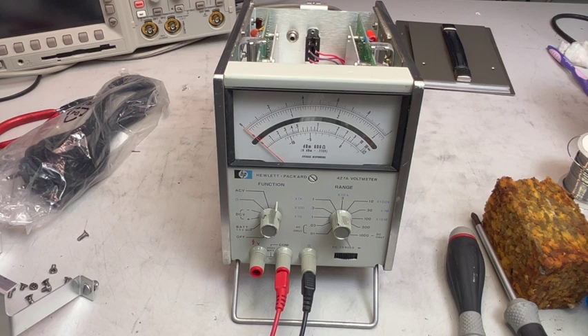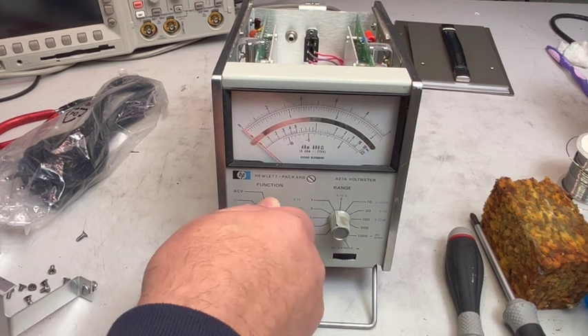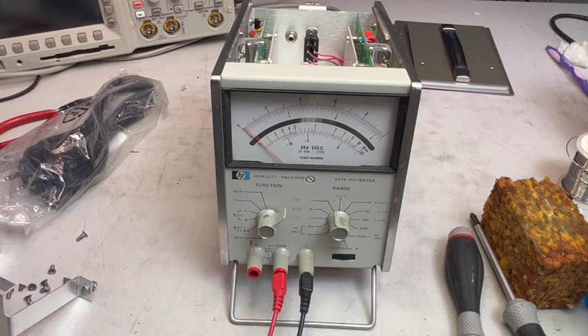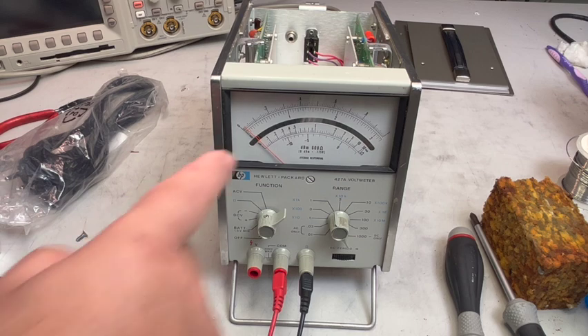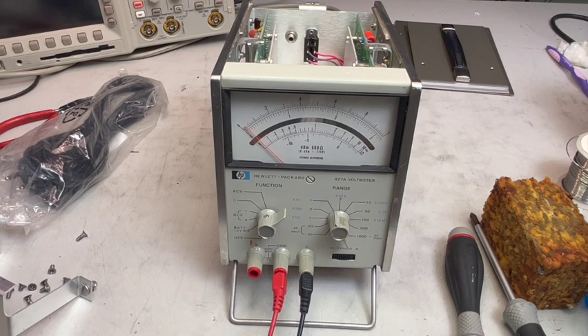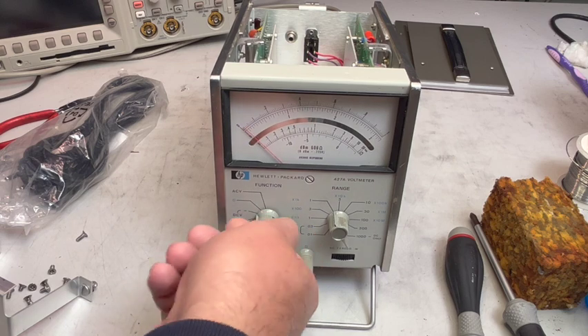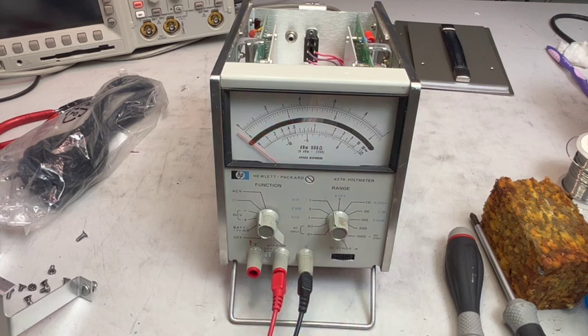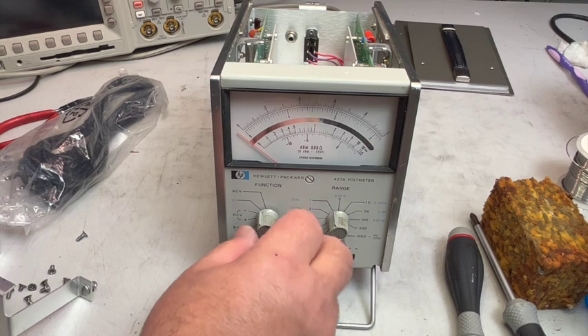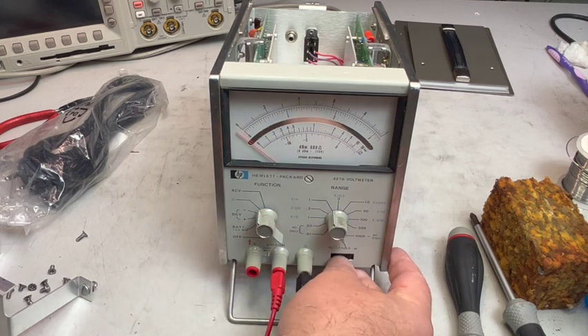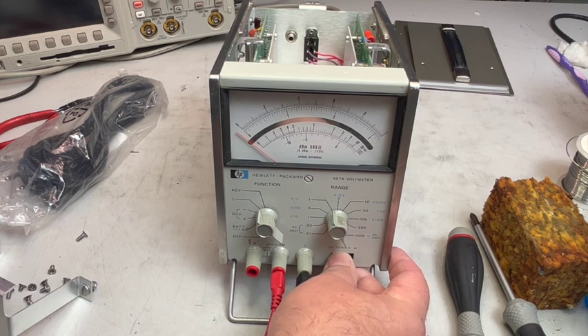As I don't know when it was powered up last time, I'm going through the dim bulb and variac. The instrument is set for 230 volt, and I'm plugging in. It's already plugged in. The variac is at 0, and the needle has already moved and is rising up. The voltage doesn't make any big change. I'm at 100 volt. I've placed terminals here, these two wires, and they are shorted together. So we should have a meter that goes up, and it doesn't.